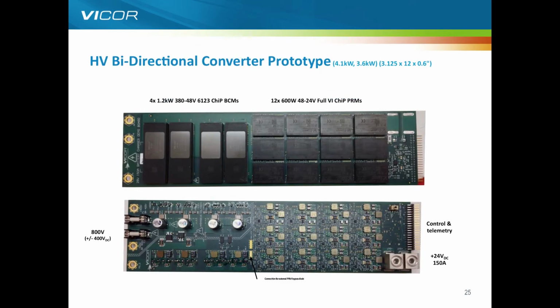The photographs on this page show the prototype we've been running. On the left-hand side at the top are the 4 bus converters going from 800 down to 48 volts, and then we have the rack of 12 regulators going down to that 24 volt point. A very simple, elegant, and small design, only 3 inches by 12 inches. Obviously you need a heat sink on the top.